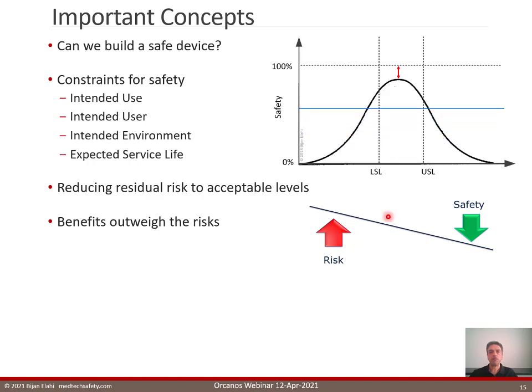And this blue line here represents the acceptable risk or minimum amount of safety that's acceptable. So if you look at this diagram, you can see that this product is acceptably safe when it is operated between the lower spec limit and the upper spec limit. And as the device gets warmer, gradually safety comes down and it intersects the blue line, which means at this point it becomes not acceptably safe. Also, if it gets colder, at some point it becomes not acceptably safe.